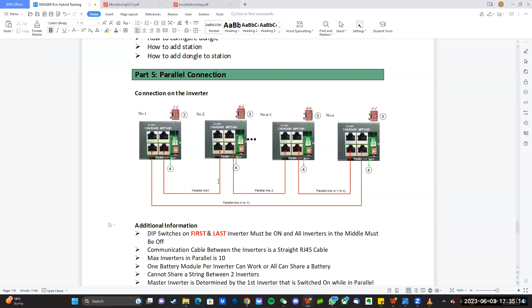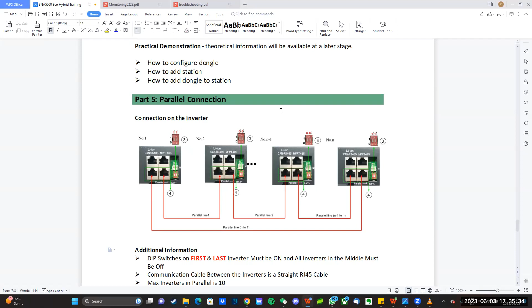The master inverter, or first inverter, and the very last inverter, their dip switches must be switched on, and all inverters in the middle must be switched off. If you have 2 inverters in parallel, then both inverters' dips must be switched on. I think that explains that section, but let me see if I left anything out.